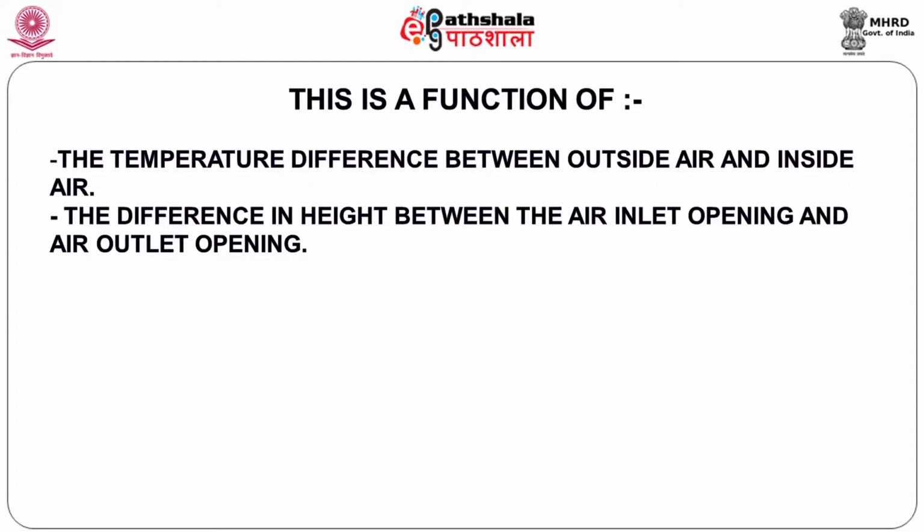As I mentioned in my talk earlier, the stack effect is a function of the temperature difference between the outside and inside, the level of the openings and the area of the openings. Now these two factors don't have to be either this or that. You could have a tall building, you could have partly natural effect of ventilation, you could partially have the other. So again, being natural elements, they are difficult to calculate exactly, but a shed designed with these parameters can be extremely useful to control temperatures to the requirement of internal equipment.